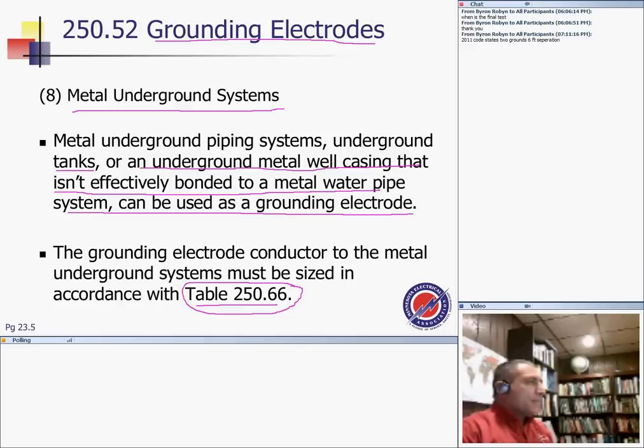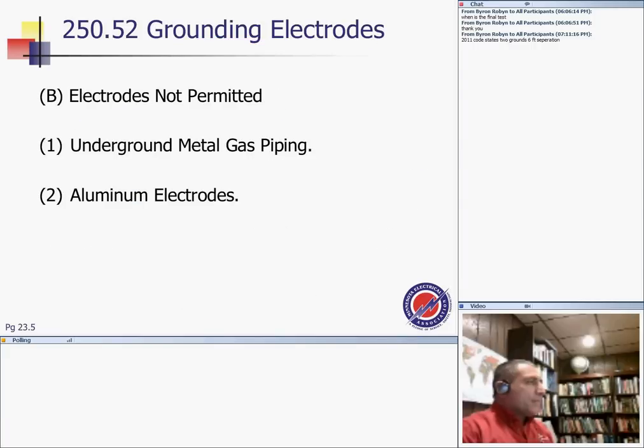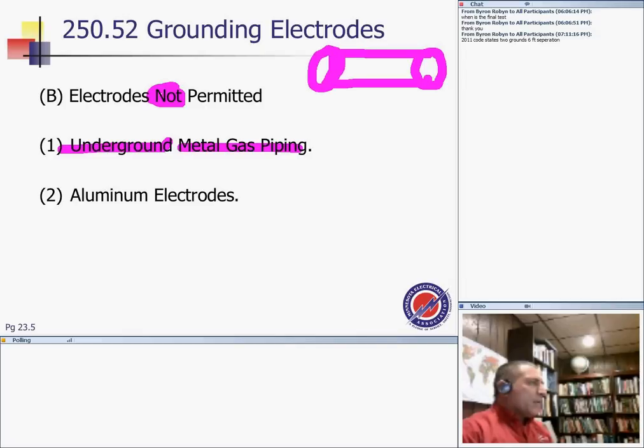This is an interesting table, and I'll put it up in a second here. 250.66. Okay, so now we know the ones that we can use. Now let's look at the ones that we cannot, shall not, will not use, not permitted. Gas pipe, metal gas pipe. I emphasize the word underground. If the gas pipe is overhead and could be energized, you have to tie to it. That's bonding. You have to bond it.